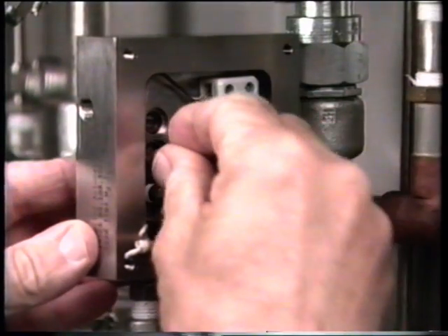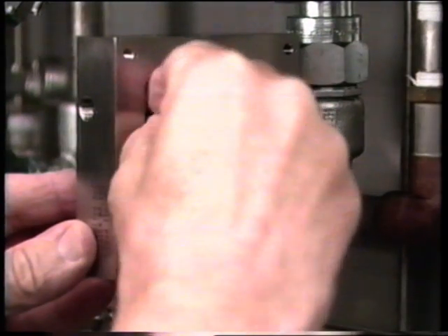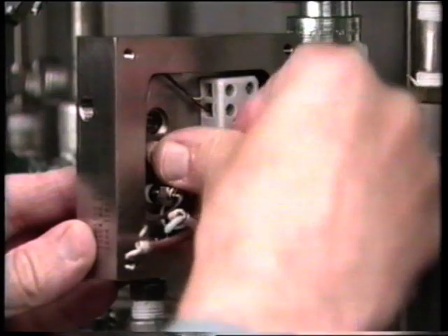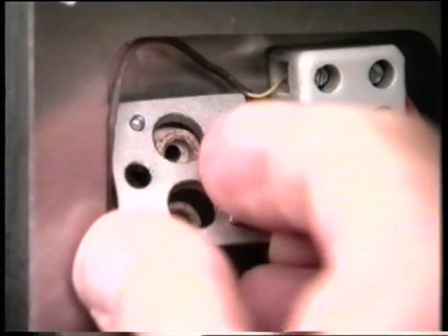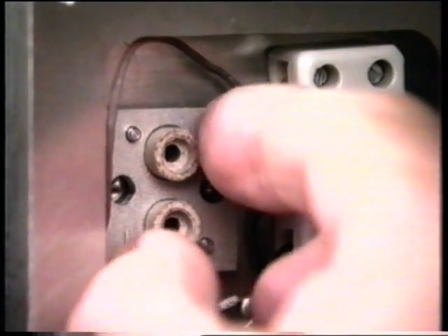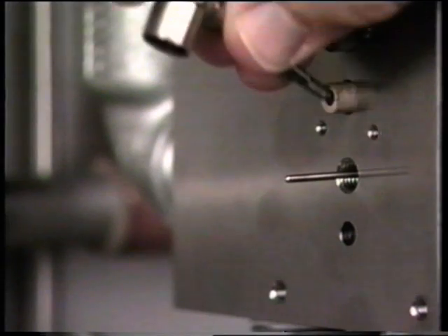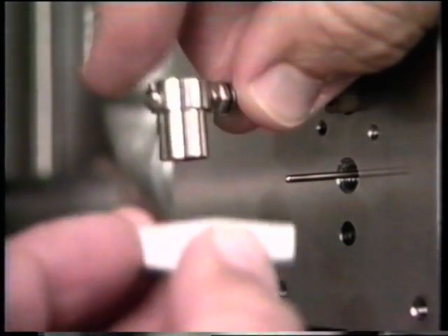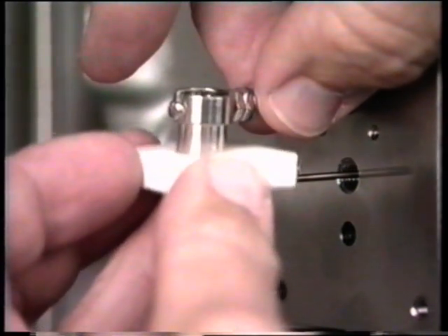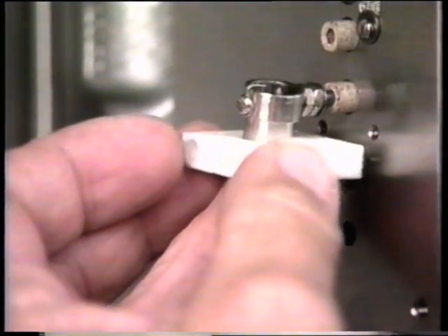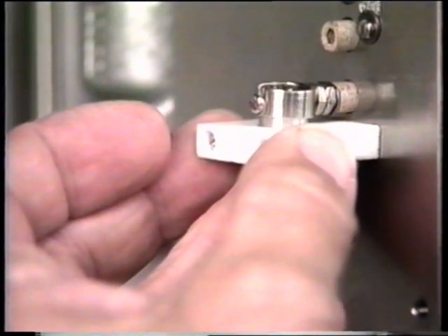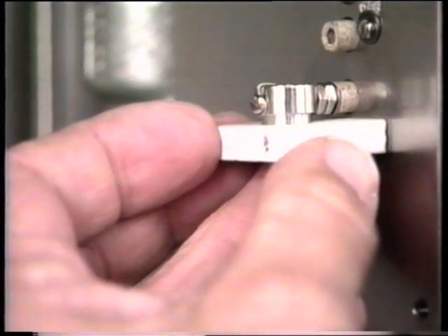Insert both the bias ignite and collector insulators through the cavities containing the O-rings and press them firmly into place. Place the insulator clamp plate over the two insulators and clamp it in place with the bias ignite and collector ground clamps. Insert the collector electrode into the insulator. Place the baffle plate against the body and slide it over the bottom portion of the collector until the baffle plate holes align with the threaded holes of the body.